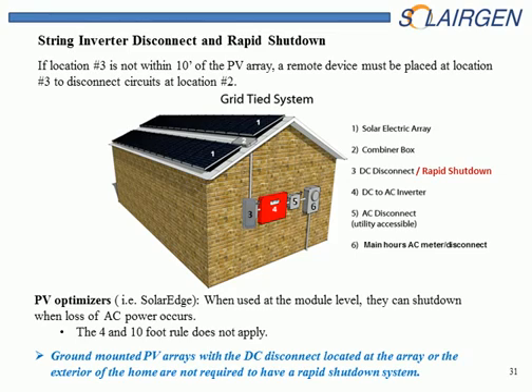If this conduit does not come from the roof straight down to a disconnect and it actually goes inside the structure, it's required that a remotely activated disconnect be placed within 4 feet of the entry point into the roof. Now that's 2014. That was not enforced until 2015, and a lot of these products, rapid shutdown systems, just now are on the market. So basically what you're looking for is either that it's microinverters or that it's a SolarEdge with PV optimized. Otherwise, there is high voltage from that disconnect point up to the PV array. So just find out where it's going, and that's your danger point.